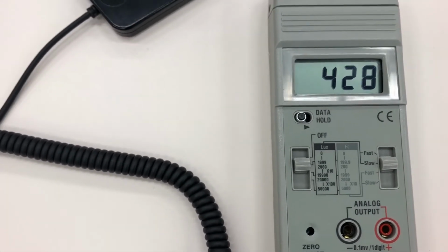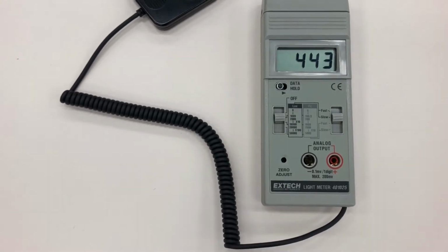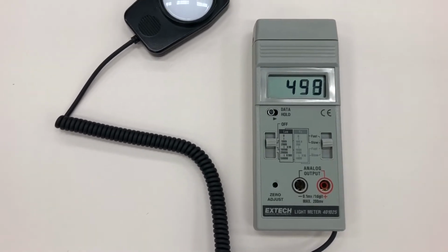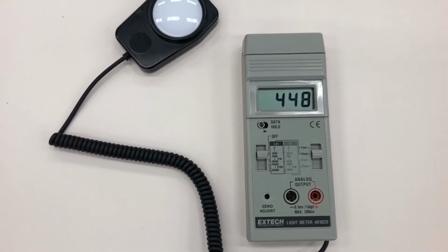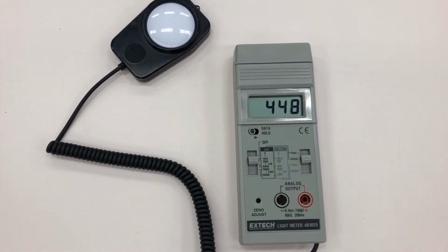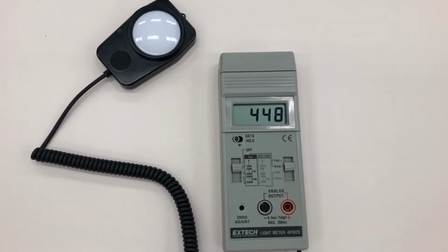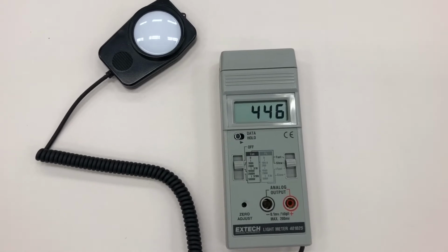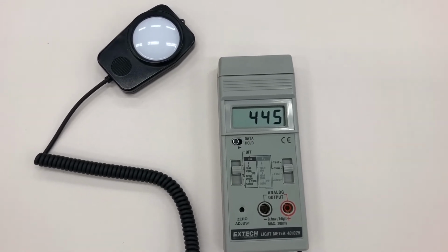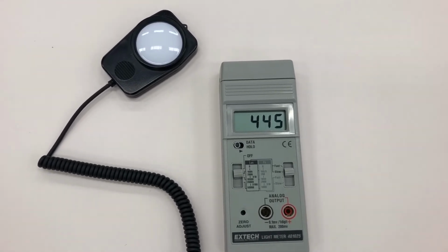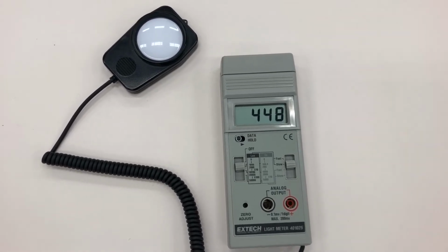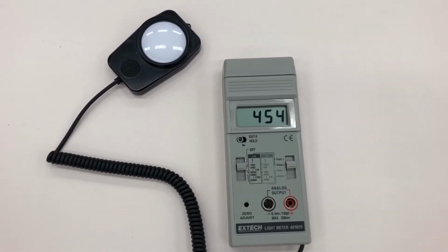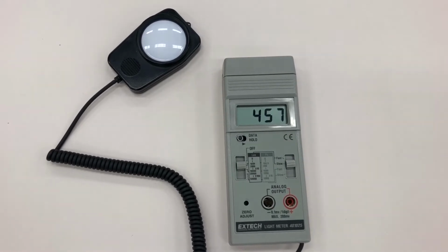That's relating back to the fact that 1 foot candle is approximately 10.76 lux. So for this light meter, if you were measuring in the Department of Kinesiology or in the HK building, lighting of approximately 300 to 500 would be appropriate in an office, so it's not surprising that our number right now in the undergraduate lab is falling within that.